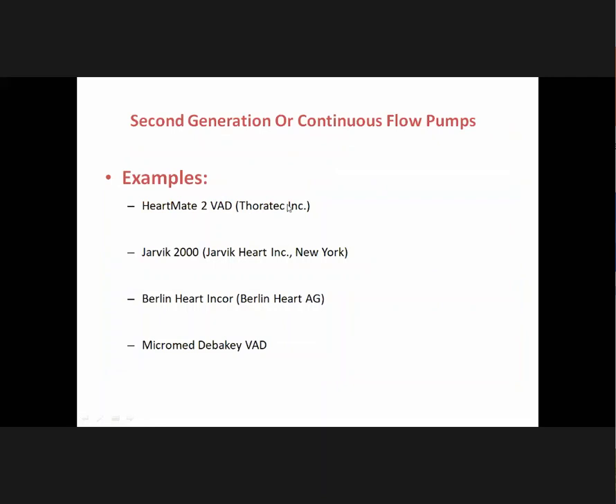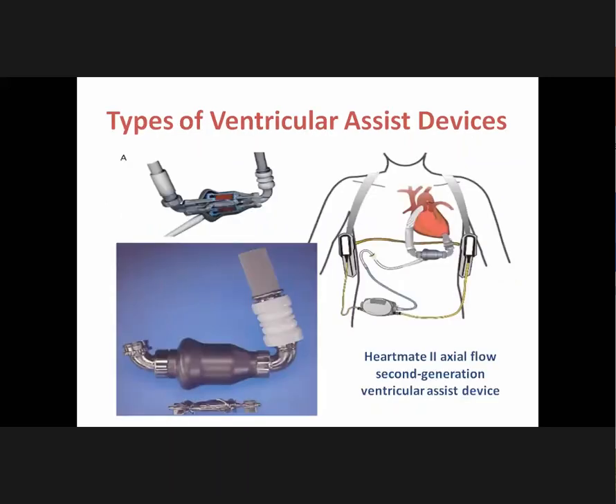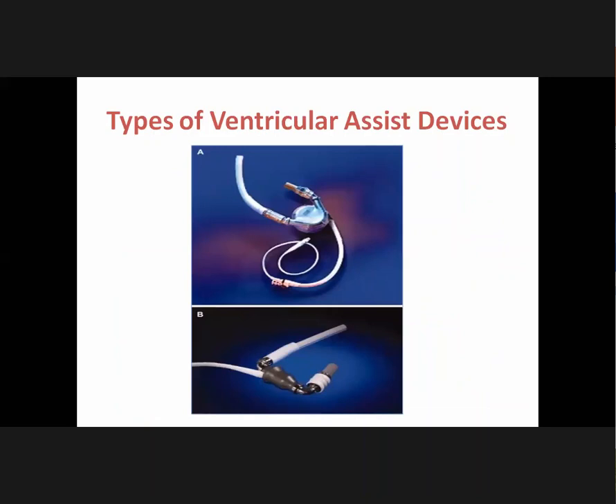The second-generation or continuous flow systems include the HeartMate 2, Jarvik 2000, Berlin Heart INCOR, and Micromed DeBakey VAD. The HeartMate 2 is a continuous flow axial blood pump with an internal rotor with helical blades that curve around a central shaft. The twisted shape of the outlet stator vanes converts radial blood velocity to axial direction; it can pump around 10 liters per minute. In the absence of a blood sac, there is no need for venting. Compared to first-generation, the size of HeartMate 2 has come down drastically, and technology has changed from a pneumatically driven system to an axial flow motor with rotor blade.